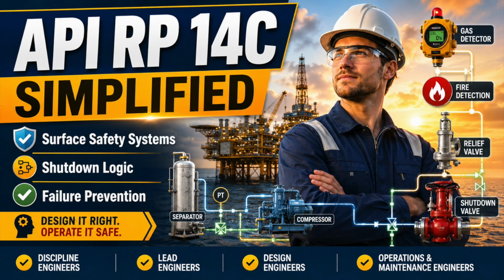Gas detection, ventilation, and layout must also be designed as one problem. A detector cannot compensate for poor ventilation. A detector placed in clean incoming airflow may never see the gas accumulating behind congested equipment. A ventilation fan can spread gas across an ignition source. An enclosed module can convert a small release into an explosion hazard. The first line of defense is to prevent accumulation through open layout and effective ventilation. Detection then provides another layer.